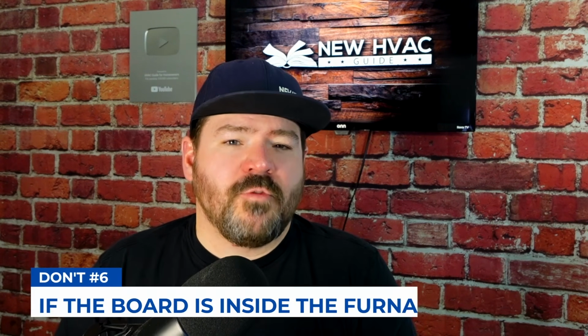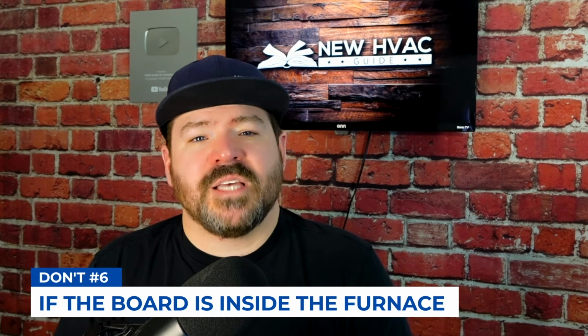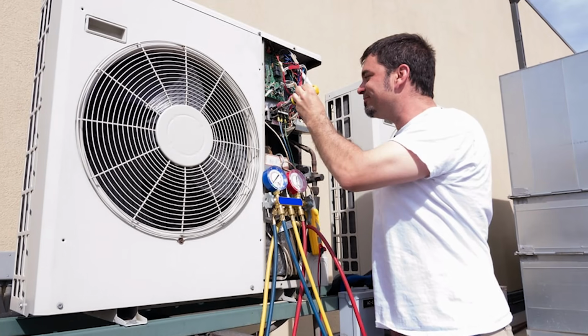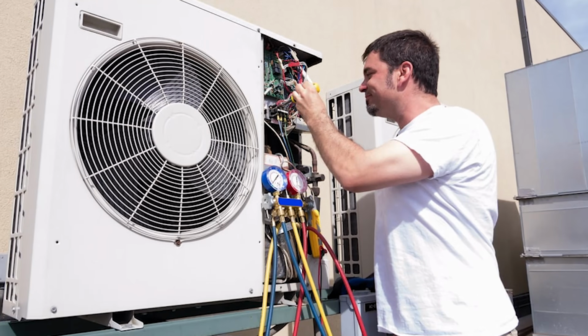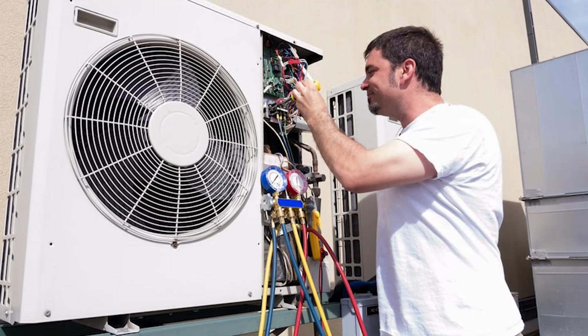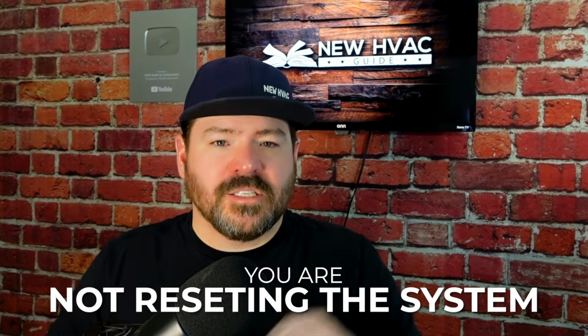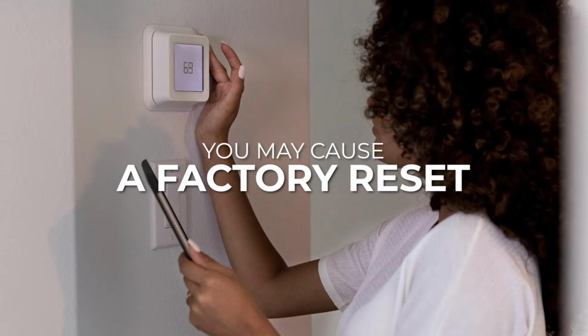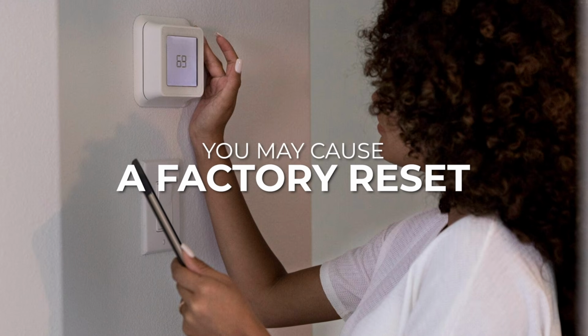And finally, we mentioned it before, but don't reset it if that reset is on a board inside the furnace. Now, I'm not talking about the timers we talked about a second ago. I'm talking about actually going into the settings of that thermostat and clicking reset, or you happen to see on the board a button that says reset. If you start doing things like that, you're not resetting the system, you're not cycling the power. You could be actually clearing the programming of that system by, say, a factory reset. You've now cleared out all the settings. The system now doesn't even know, am I paired with a single stage outdoor unit, an inverter, or what? You've now cleared everything out, and now a pro is going to have to reprogram everything because you've reset that device, whether it's the board or the thermostat or whatever.